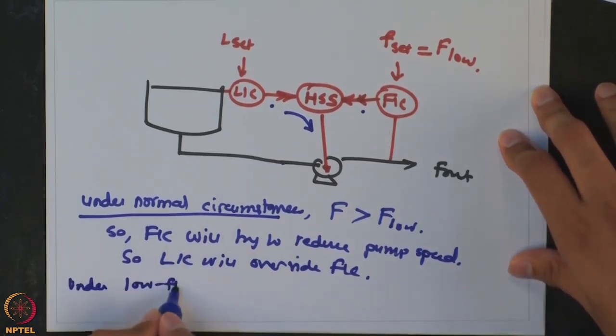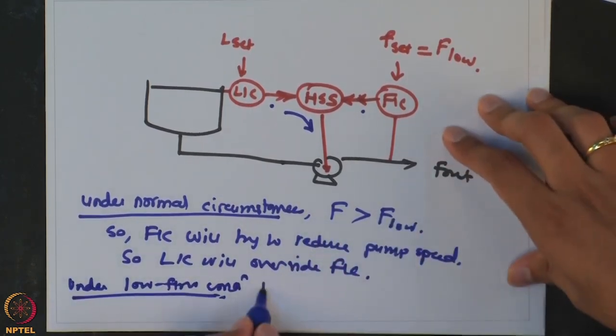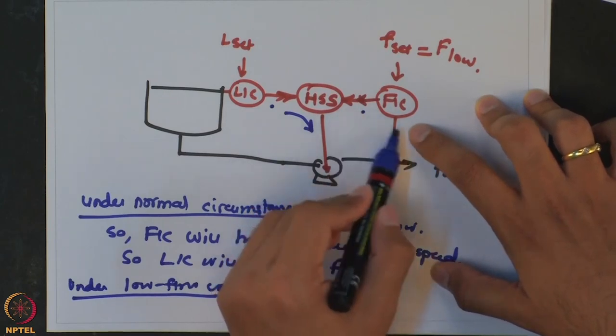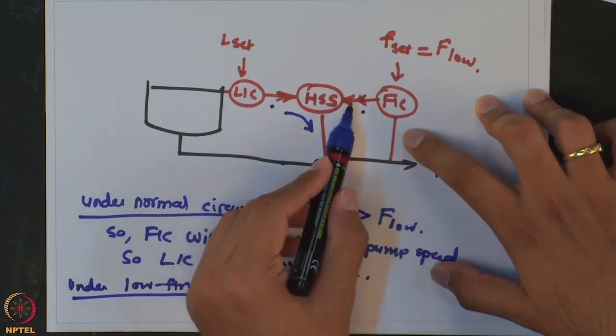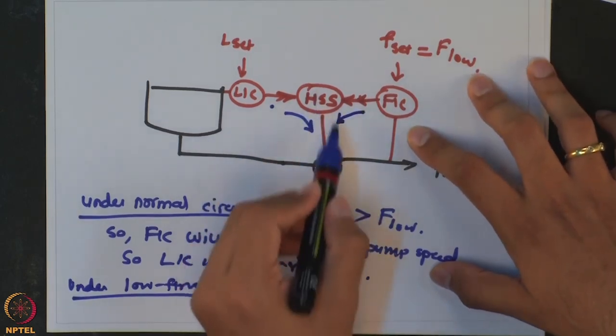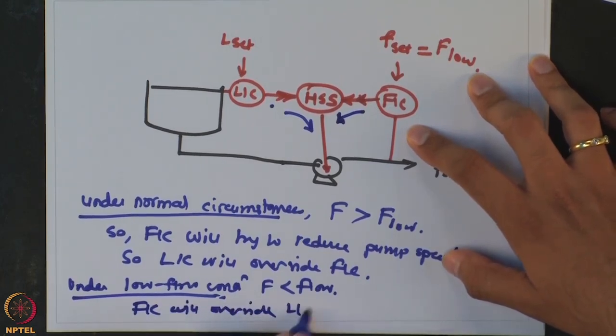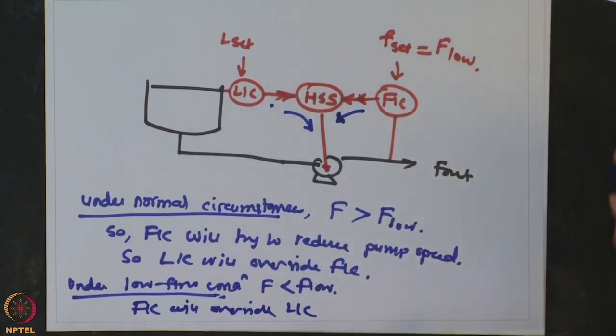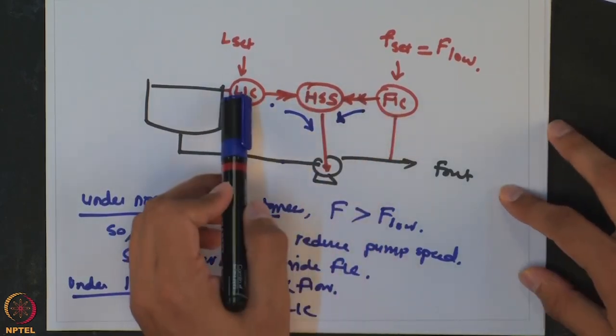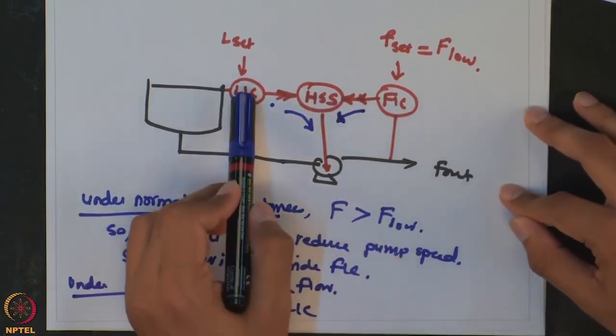Under low flow conditions, when flow drops below F_low, the flow controller output tries to increase pump speed — giving a higher value that the high selector picks up. FIC overrides LIC, preventing cavitation of the pump. By using this high selector switch, we are able to control both level and flow at or above their respective safe values.